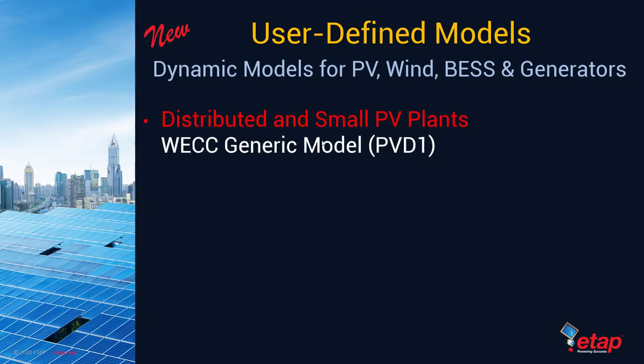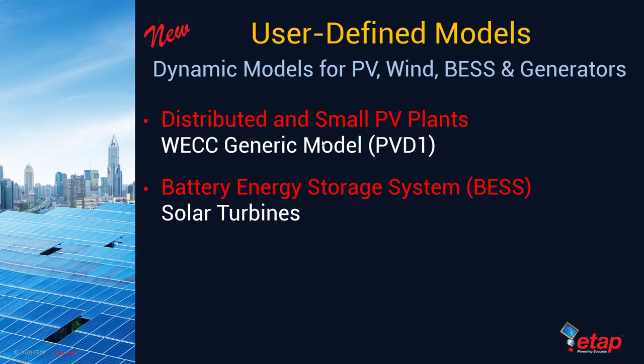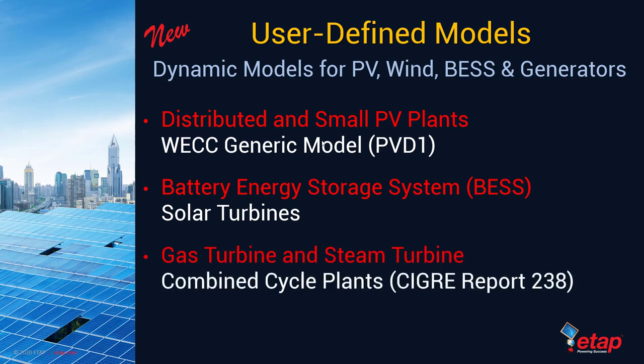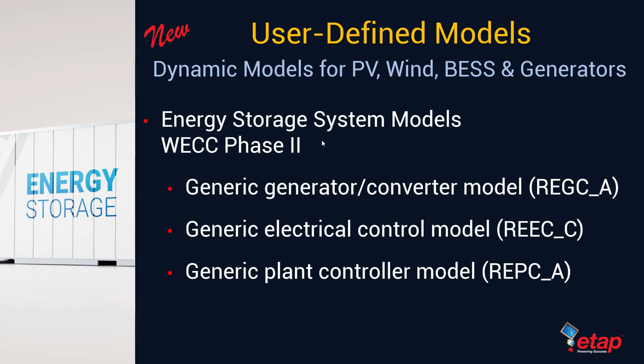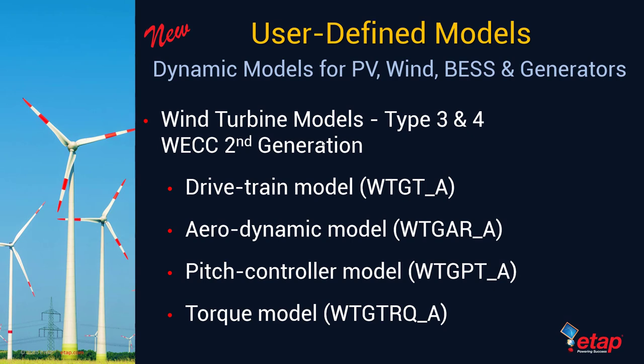ETAP20 includes brand new dynamic models for solar PV, wind, battery energy storage, and synchronous generators. WECC-based generic models PVD-1 for distributed and small PV plants have been included. Solar turbine-based battery energy storage system dynamic models, as well as gas turbine and steam turbine-based combined cycle power plants provided in CIGRE Report 238, have also been added. We've also added WECC Phase 2 energy storage system models that include generic generator or converter models, generic electrical control models, and generic plant controller models.